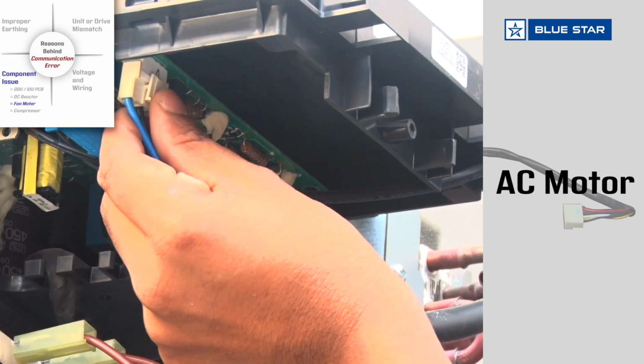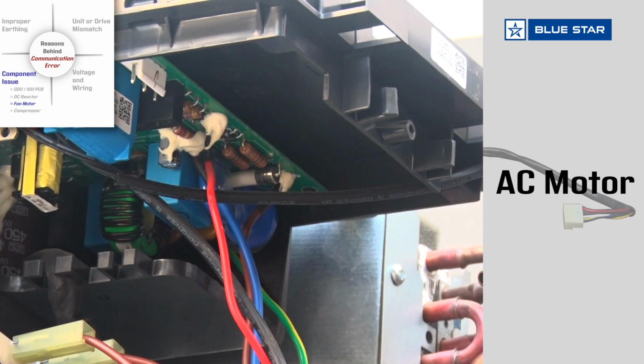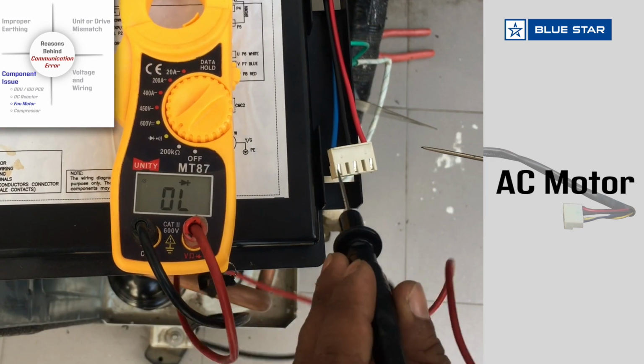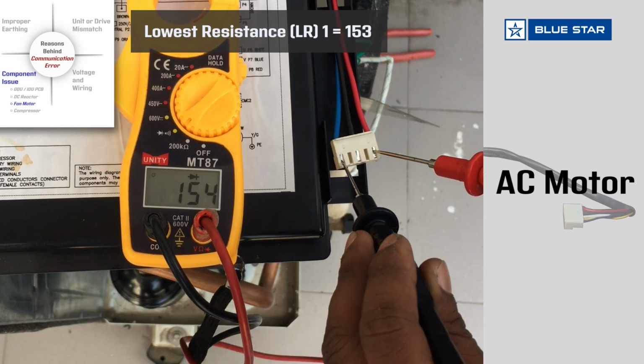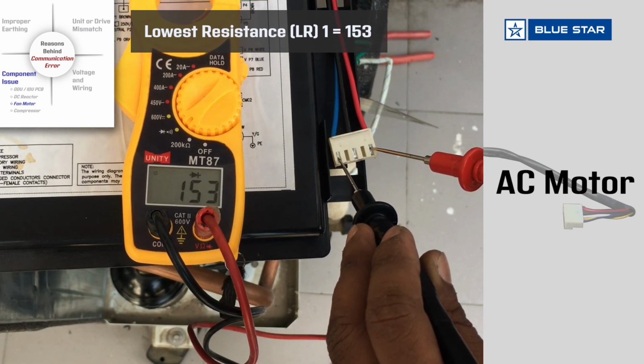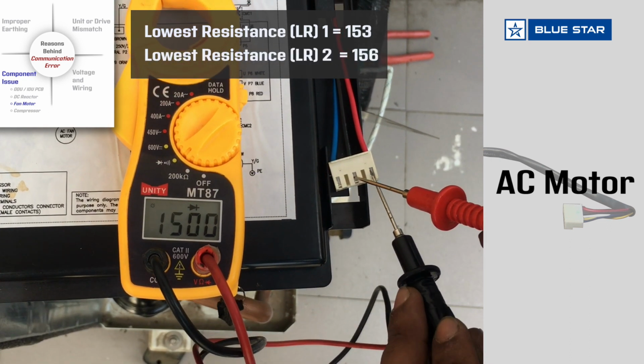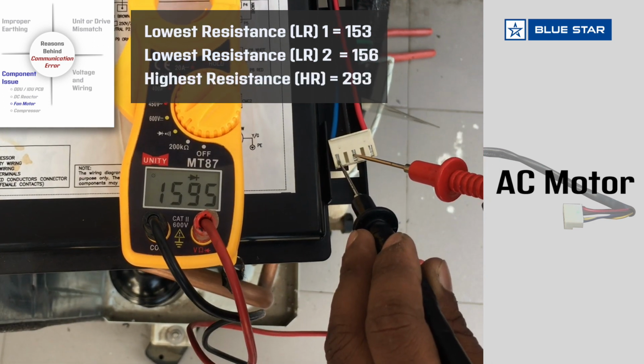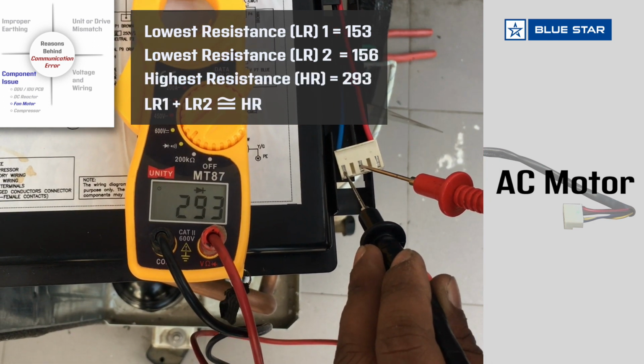If the system has an AC motor, then remove the motor connector from the ODU PCB and check its resistance across 3 terminals. If the highest resistance is the sum of the 2 lowest resistances, then you can conclude the AC motor is in healthy condition. Otherwise, it is faulty and has to be replaced.